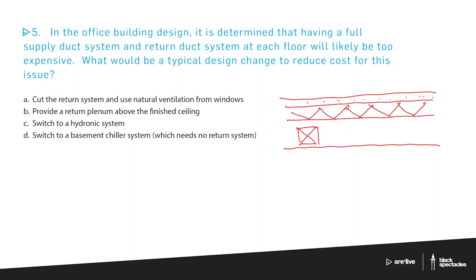So there I am sitting at my desk working. The concept of the plenum is I might supply air all the way out here so it comes down right by an outside window—imagine that's a big window. So I'm dealing with condensation on the window, which is bad from an insulating standpoint, by putting conditioned air right where the problem is, creating a buffer between me and that window. The window is also a radiant issue—it pulls heat from me in winter—so having that air as a buffer between me as a radiator and the window as a radiator is very useful.